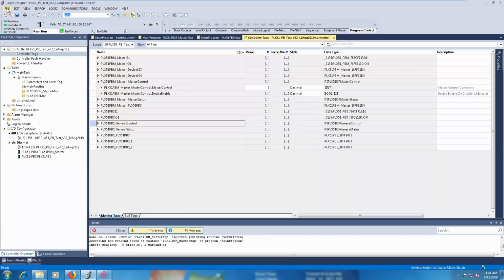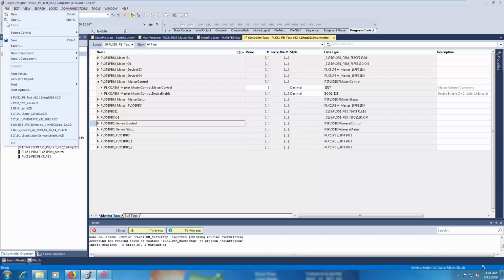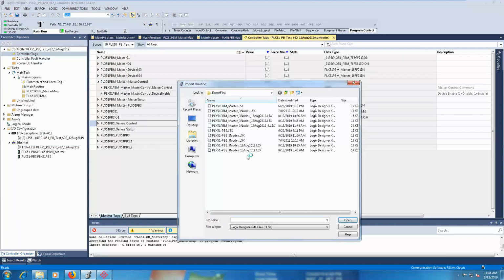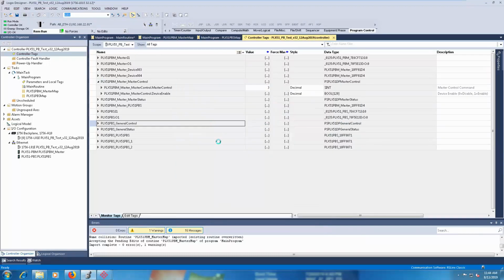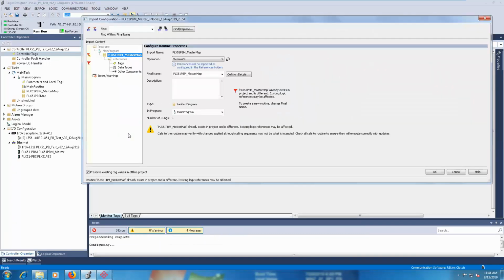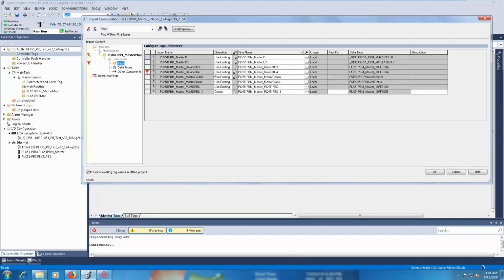So importing a new file into Studio 5000 is as easy as File, Import Component, and then I would select a routine. And I would go ahead and select my latest file here. Since I've previously imported this file, I will have to overwrite my existing one. The nice part about doing this as an import routine as opposed to some other way, like an import add-on instruction, is that I can overwrite this routine online. And so it gives me the selection to overwrite.